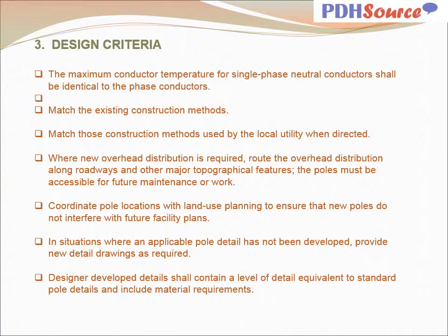The maximum conductor temperature for single-phase neutral conductors shall be identical to the phase conductors. Match the existing construction methods. Match those construction methods used by the local utility when directed.